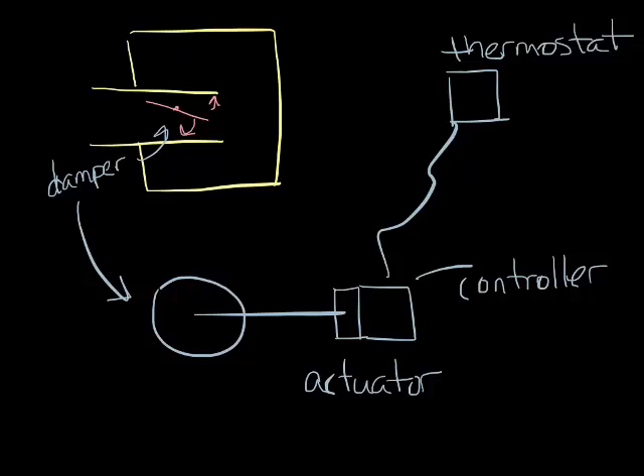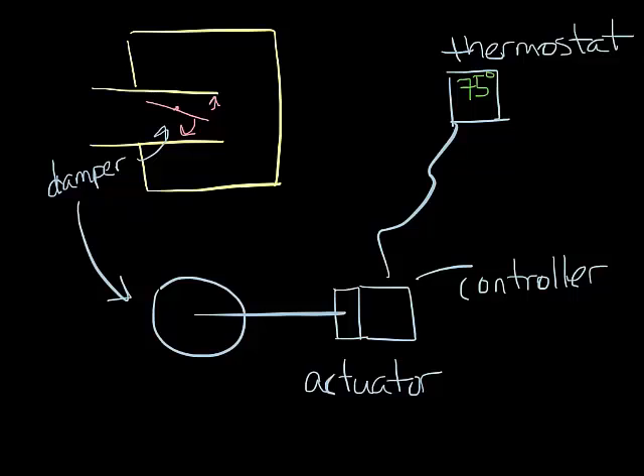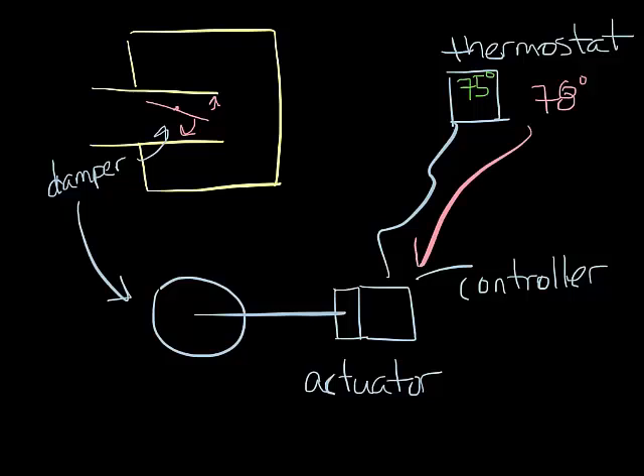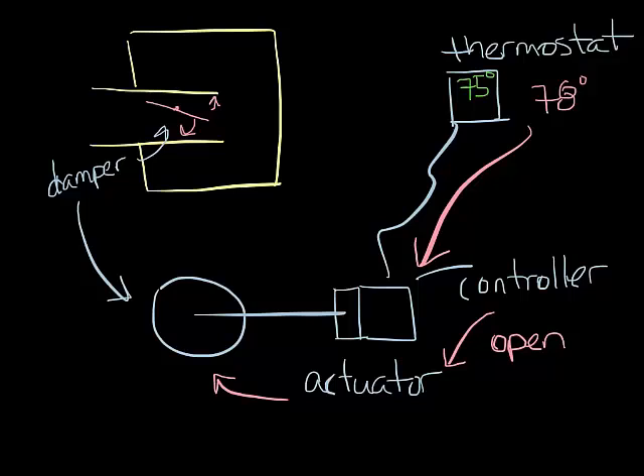Let's say that the thermostat is set to 75 degrees, but because all those people came into the conference room, the thermostat is now measuring 78 degrees in the space. This temperature and set point information is sent to the controller, which says it's too hot, we need more air. So it sends a signal to the actuator to open the damper. The damper rotates until the room temperature equals the set point temperature. This control loop happens continuously throughout the day to maintain comfort in the room.